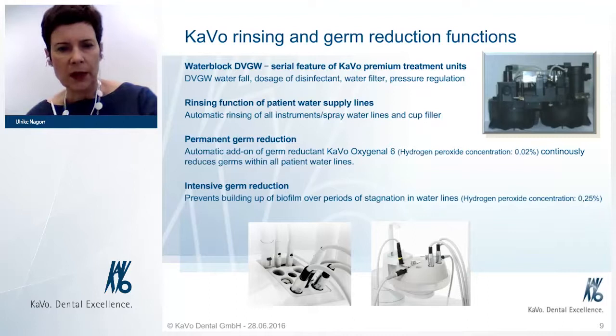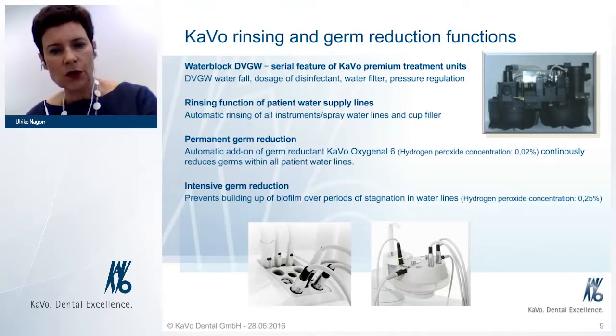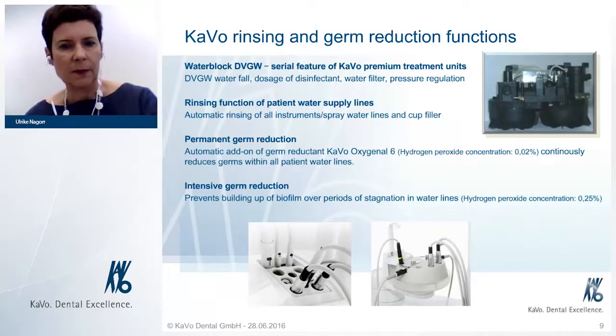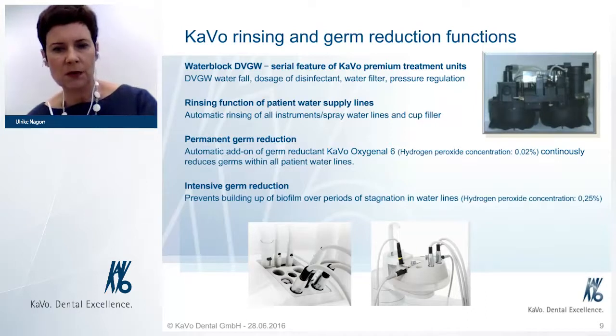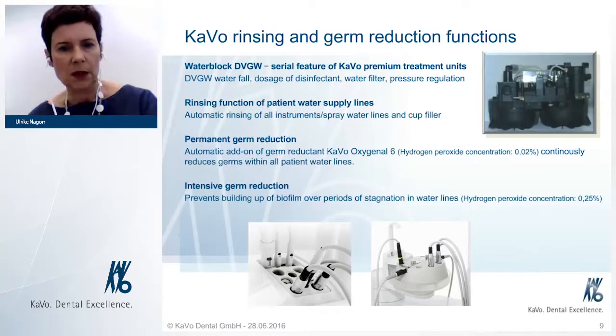This permanent germ reduction has quite big functionality, not only for the treatment units but also for the dental instruments. Quite often we see high-speed instruments come into service repair with blocked spray nozzles, and very often the nozzle is blocked not by tooth debris but by biofilm supplied from the tubings of the treatment unit.